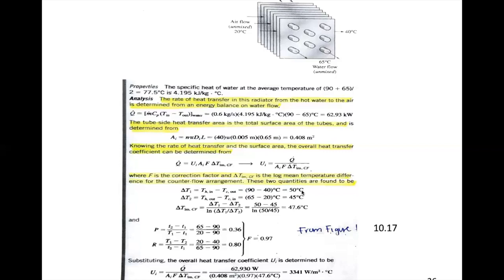Let's start with ΔT_lm. ΔT1 is hot in minus cold out: 90 minus 40 equals 50. ΔT2 is hot out minus cold in: 65 minus 20 equals 45. Applying the LMTD equation — (ΔT1 minus ΔT2) over ln(ΔT1/ΔT2) — gives us 47.6°C.